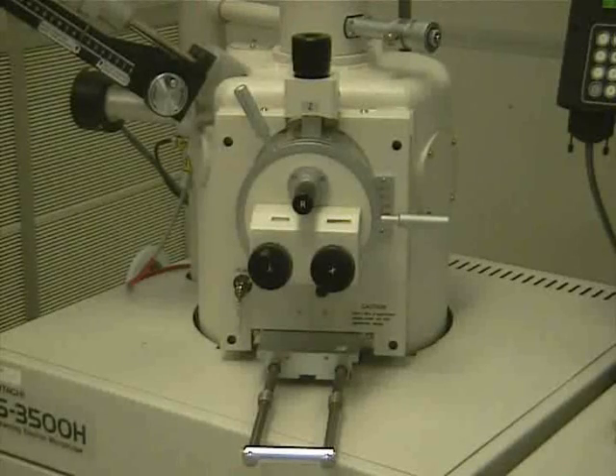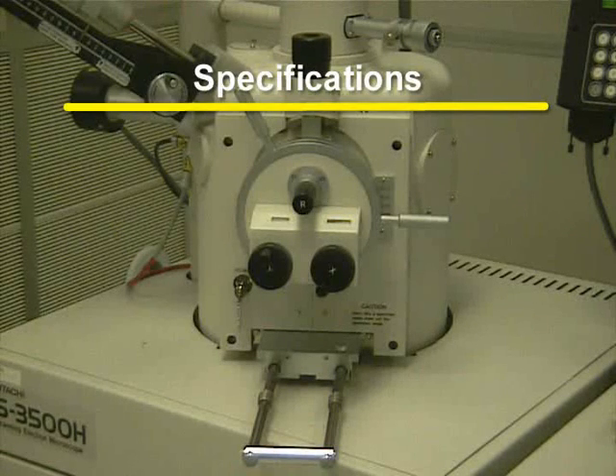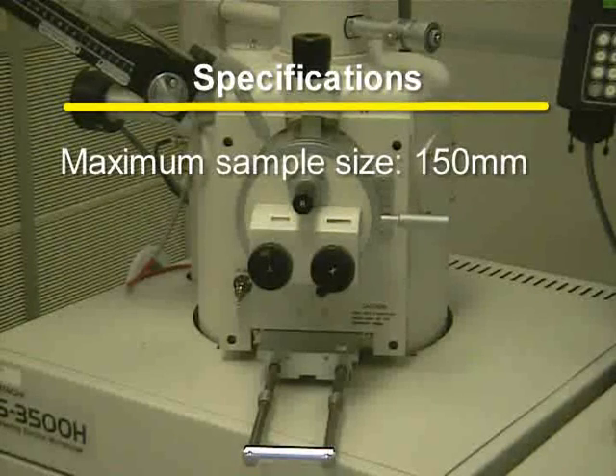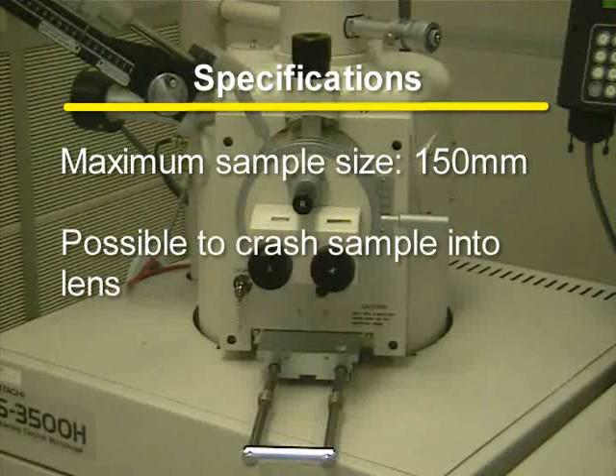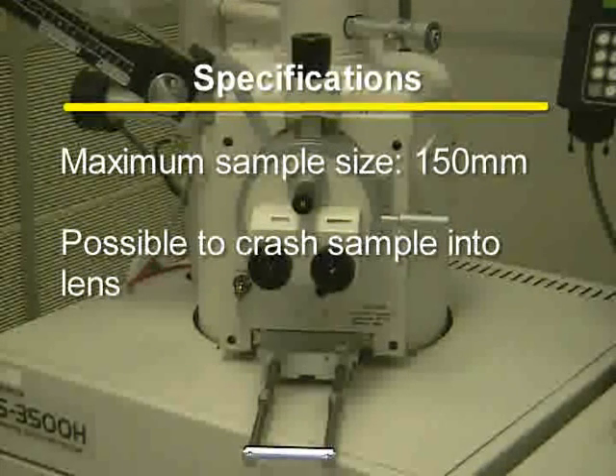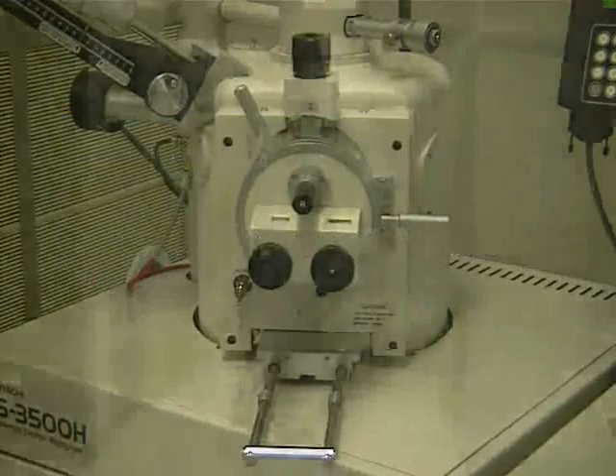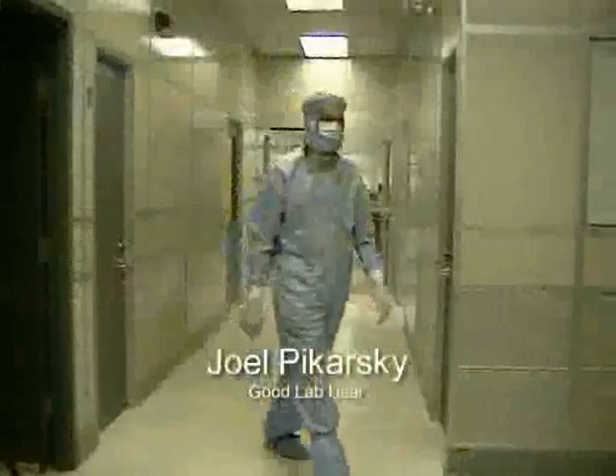The Hitachi 3500H series scanning electron microscope offers high-resolution imaging in a vacuum. With the SEM, the maximum sample size is 150 millimeters in diameter. However, when dealing with large samples, it is possible to crash the sample into the objective lens when tilting the sample. Let's now introduce our lab users.